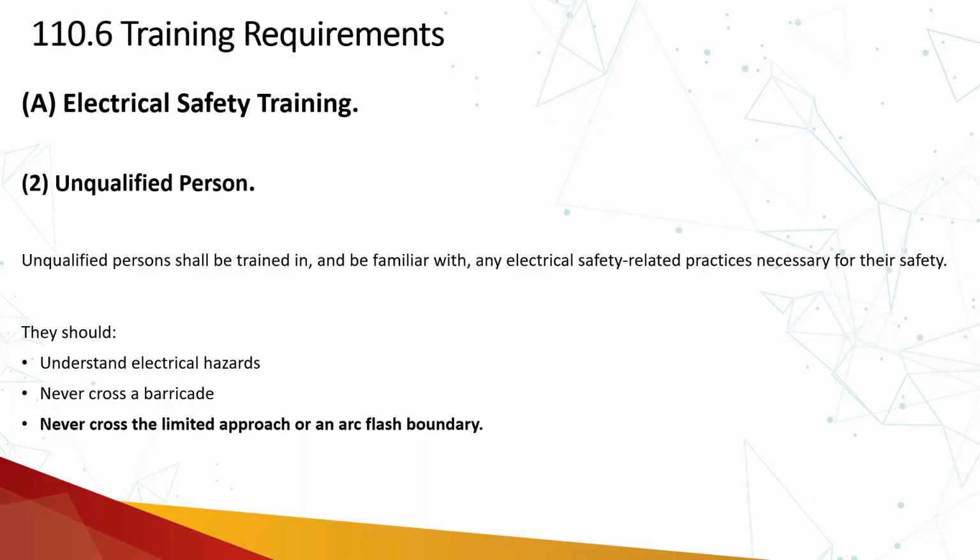They are not allowed to perform tasks near energized electric equipment. They are not going to start to work on an electrically safe work condition, and on the equipment which has already been put into an electrically safe work condition, till they have got a proper clearance. So the training requirement for unqualified person will be related to these certain points. They won't be trained, or they don't need to be trained to perform the task, but to identify the hazards there.